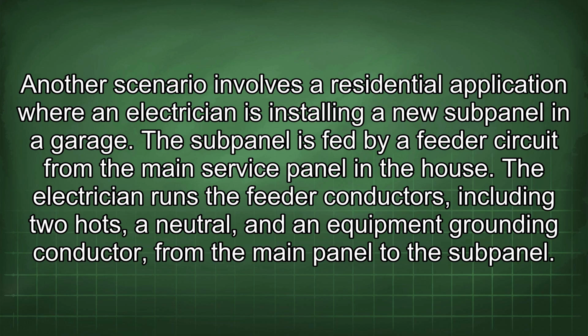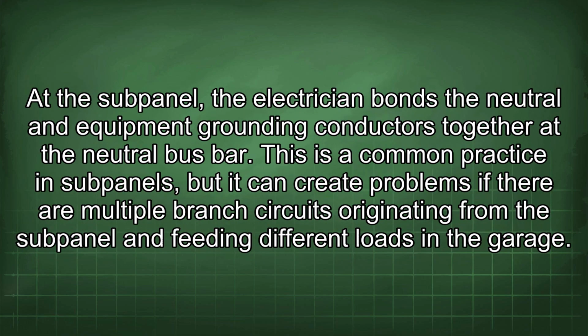Another scenario involves a residential application where an electrician is installing a new subpanel in a garage. The subpanel is fed by a feeder circuit from the main service panel in the house. The electrician runs the feeder conductors, including two hots, a neutral, and an equipment grounding conductor, from the main panel to the subpanel. At the subpanel, the electrician bonds the neutral and equipment grounding conductors together at the neutral bus bar. This is a common practice in subpanels, but it can create problems if there are multiple branch circuits originating from the subpanel and feeding different loads in the garage.